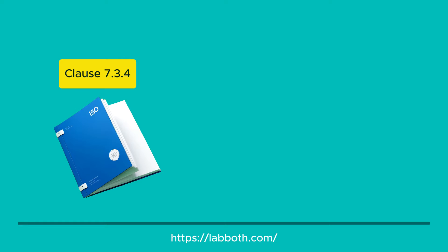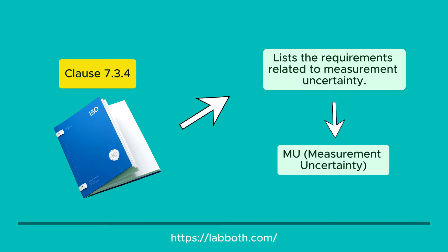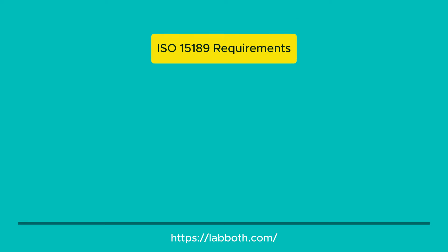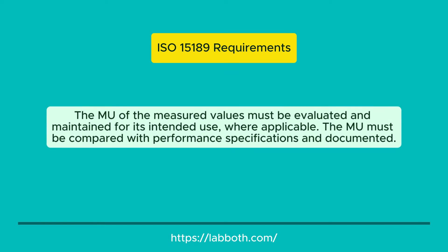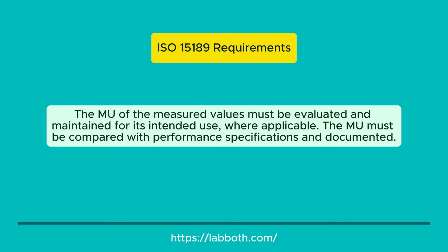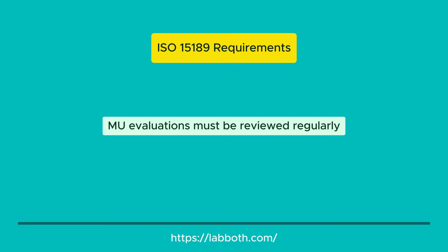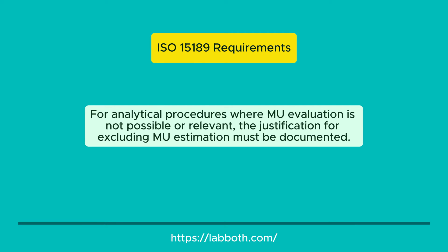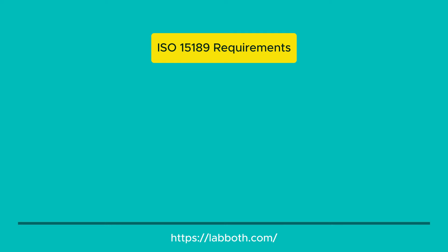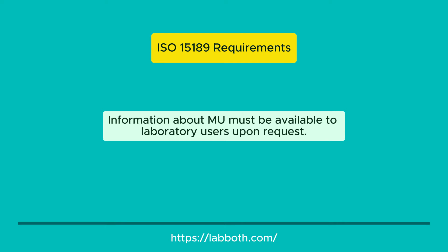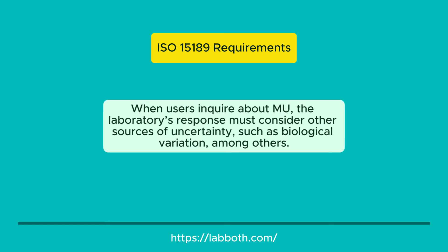ISO 15189 Standard Requirements for Uncertainty Management. Clause 7.3.4 of the standard lists the requirements related to measurement uncertainty, referred to as MU. The MU of measured values must be evaluated and maintained for its intended use, where applicable. MU must be compared with performance specifications and documented. MU evaluations must be reviewed regularly. For analytical procedures where MU evaluation is not possible or relevant, the justification for excluding MU estimation must be documented. Information about MU must be available to laboratory users upon request.